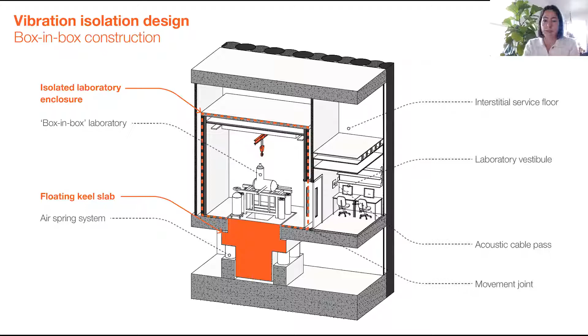One of the things we needed to do for the mechanical and electrical services, to prevent any movement in the ducting or pipework entering the building structure, was install high efficiency spring hangers, which you can see in the photos. These hangers are 99% efficient, removing 99% of the vibration created by the service and preventing it from entering the structure. But they need to be carefully selected based on the mass and movement of the service they're trying to isolate, and most manufacturers of pumps, chillers and fans don't know the vibration movement of their plant, because it's not something they often have to provide.